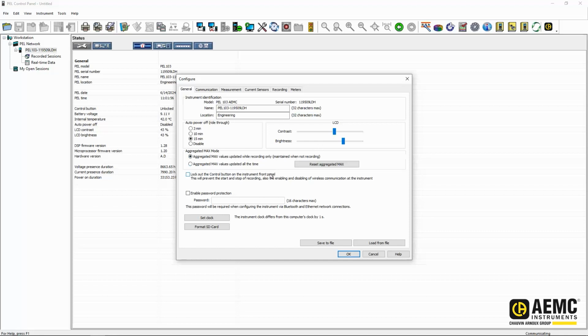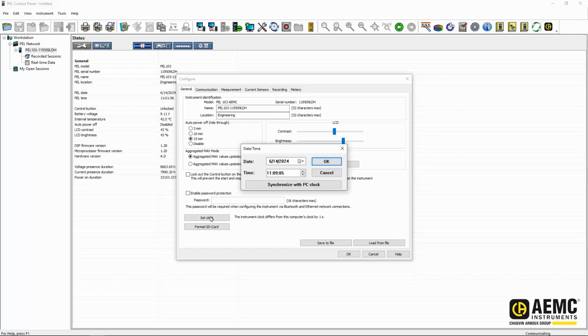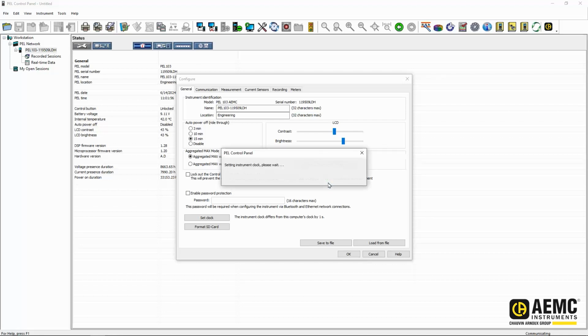Other functions on this screen allow us to lock out the control button on the instrument, require a password to configure the instrument later, and most importantly, the internal clock synchronization. We suggest ensuring the clock is synchronized before every recording. To do so, simply press the Synchronize with PC clock button.